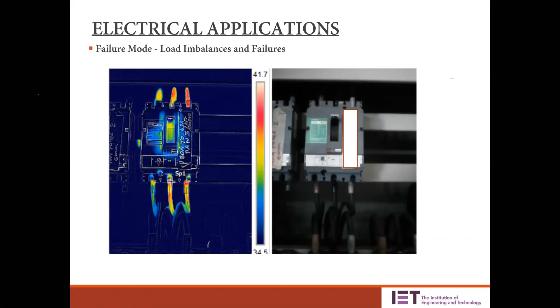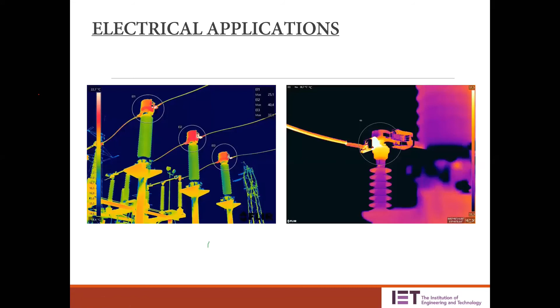application. Failure mode: usually when you have three-phase cables entering into a panel, there can be inductive heating through eddy currents. This is a really interesting photograph by my man Ivan from Thermospec Australia, and we have seen this enough. Usually what we do to prevent this from happening is to have a cut through the cable entry plate, so that the circulating eddy currents would not be possible.